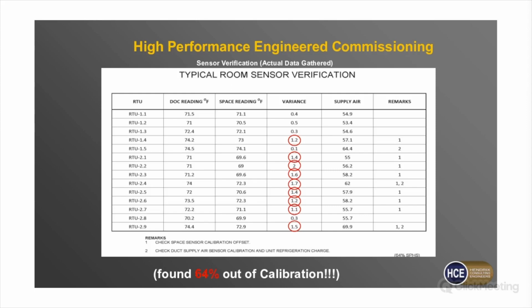In this particular wing of units, 64% of them were over a degree to a degree and a half out. I was at another space, an office building recently where 100% of the sensors were off, and they were off by 3 to 4 degrees each. They were all reading high.